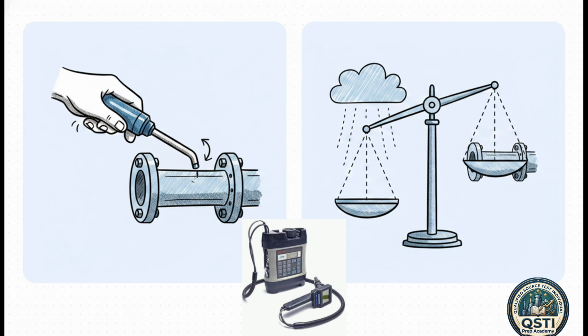For Type 2, the inspector actually first measures the local ambient air about 1 to 2 meters away from the source to get a baseline. Then they compare that baseline to the reading right at the surface of the equipment. If the difference is practically zero, it's considered clean.